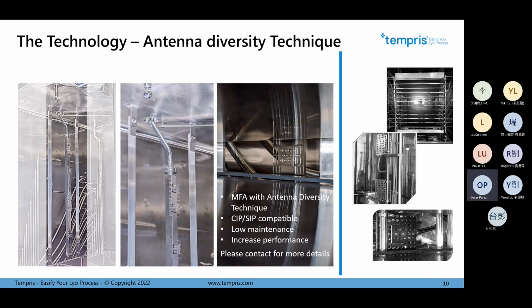Here, just to show how it looks, is one antenna installed in a large freeze dryer with this new technology. On the left side, we have this MFA antenna. Of course, everything installed inside the freeze dryer is compatible with CIP and SIP, clean and sterilization in place processes. The new antenna is low maintenance. You don't have any cables, so no possible damage to the cables during service of the freeze dryer, for example.